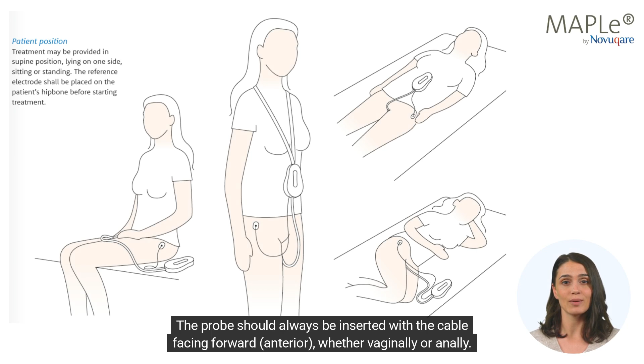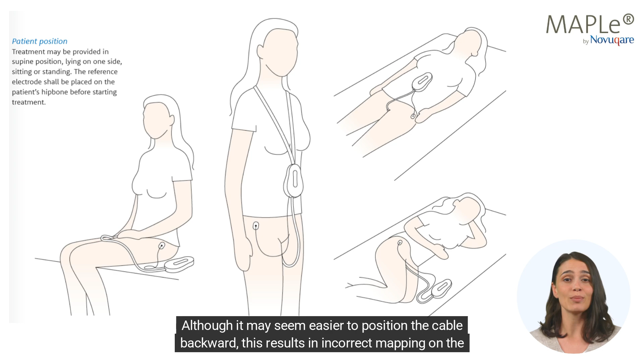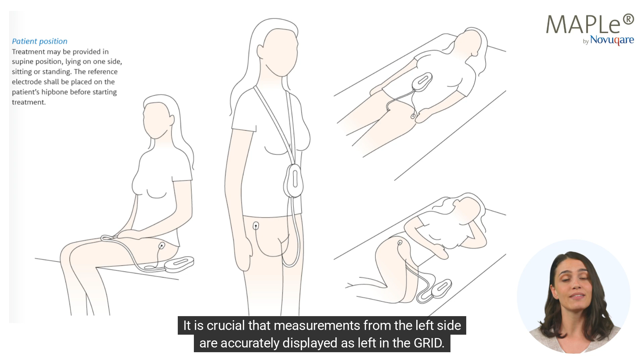Probe positioning. When using the MAPLe probe, it is important to understand that slight variations in positioning can affect measurements. For example, in patients with prolapse, probe positioning may vary. The probe should always be inserted with the cable facing forward, anterior, whether vaginally or anally. Although it may seem easier to position the cable backward, this results in incorrect mapping on the MAPLe grid. It is crucial that measurements from the left side are accurately displayed as left in the grid.